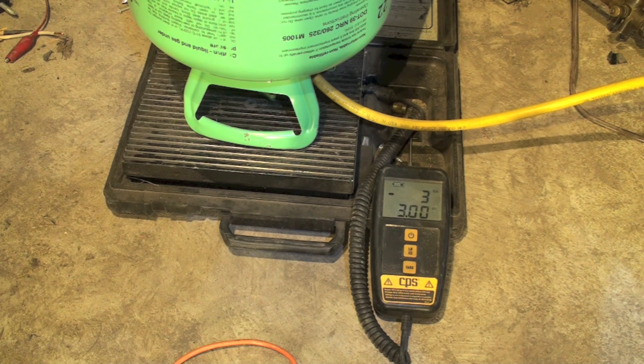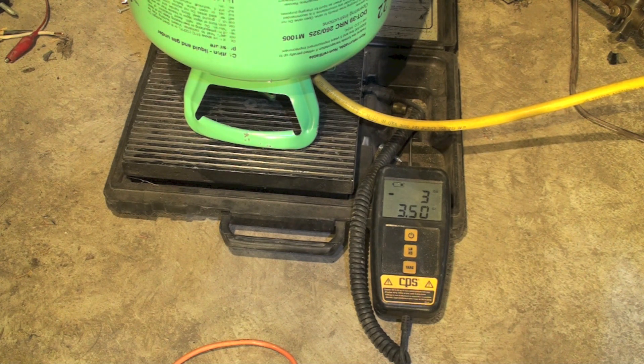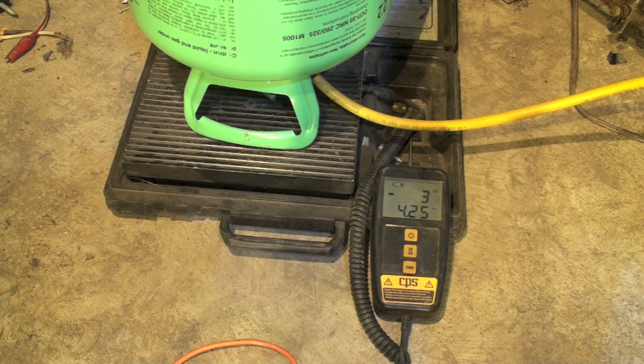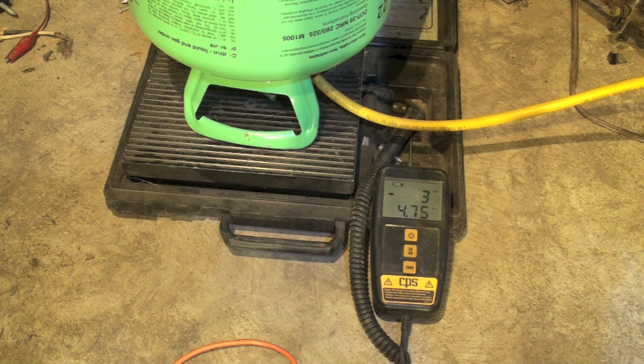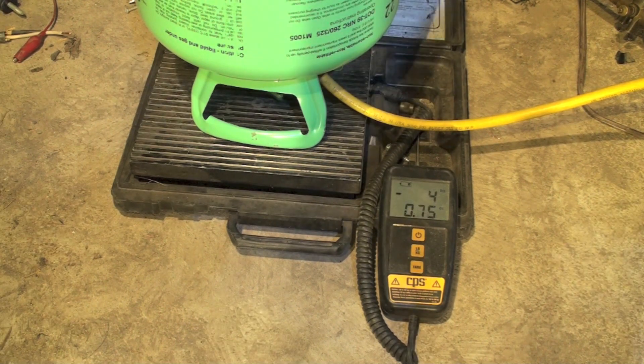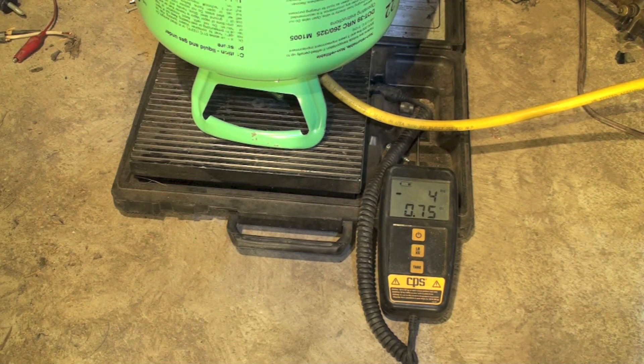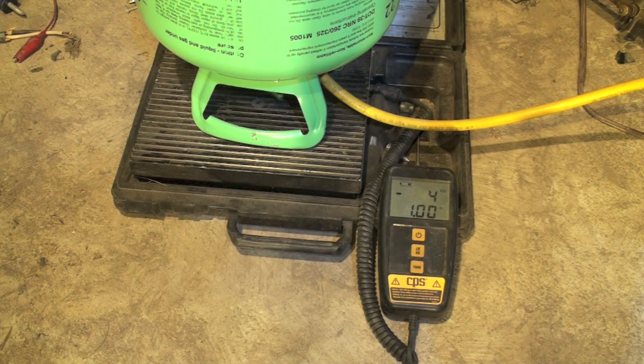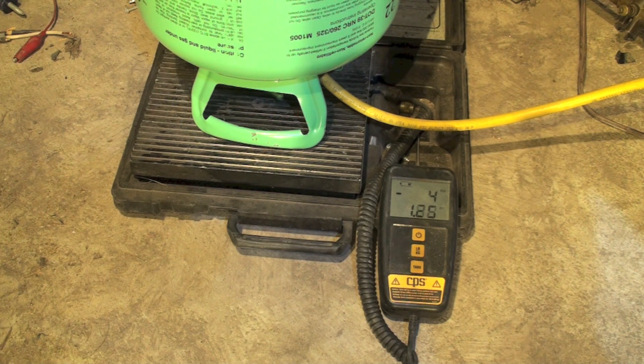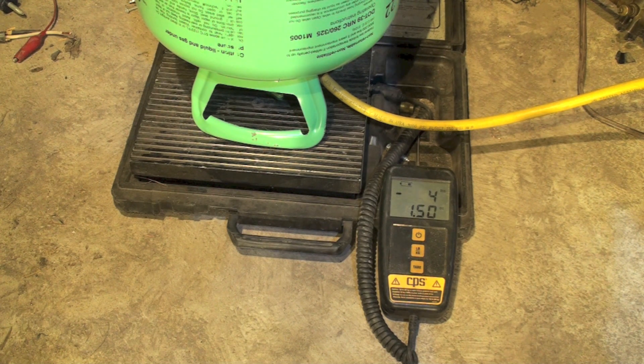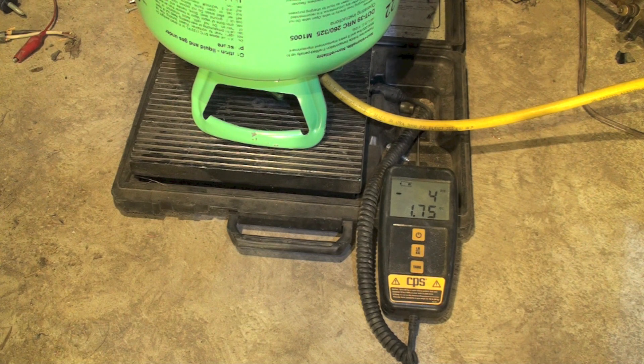This thing may not make more than about five pounds. Remember we have seven and a half pounds for the factory charge. It looks like we're going to settle out at about four pounds. Doesn't seem like it's going to get a whole lot more in, so I'm going to go ahead and begin charging this thing through the low side with gas.